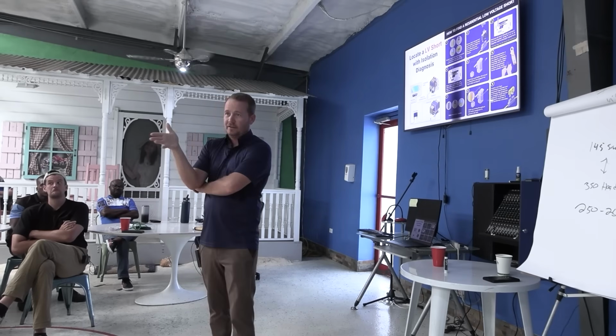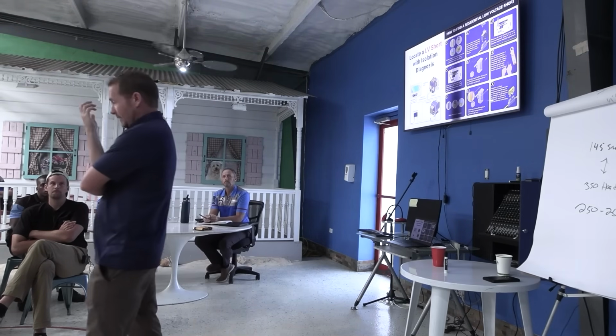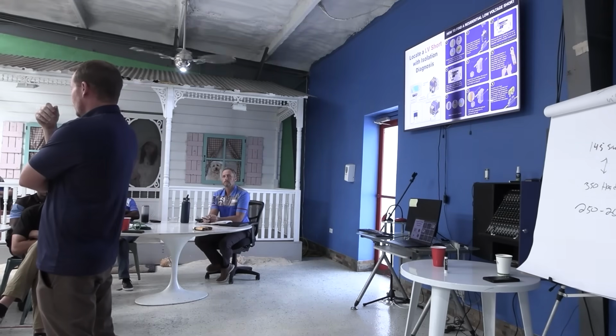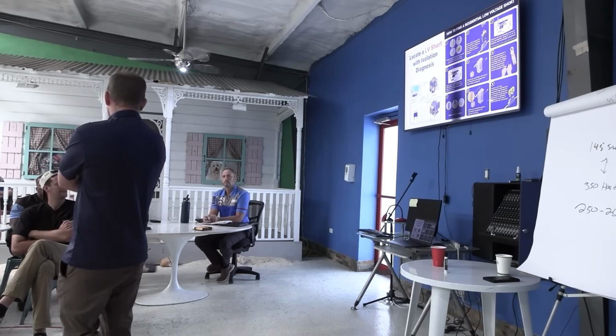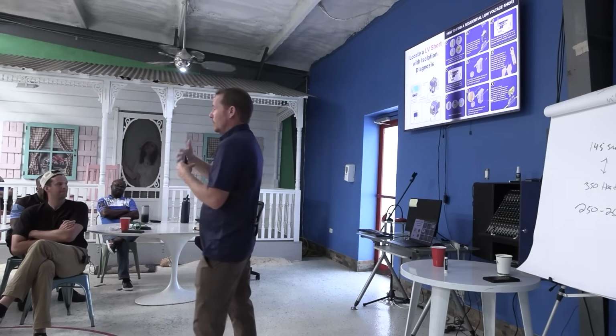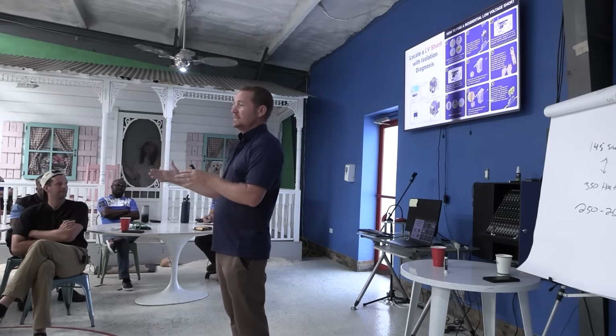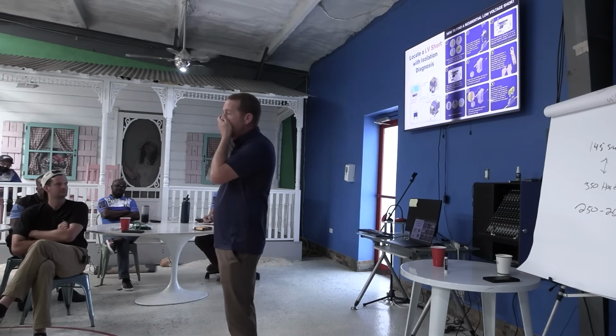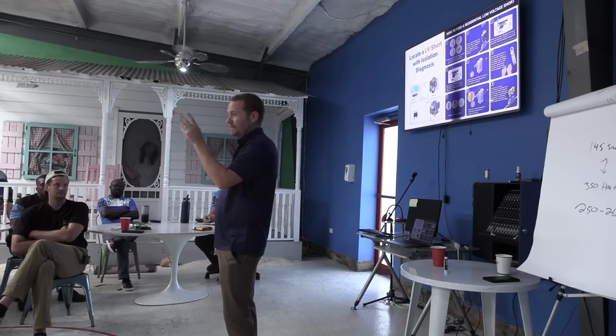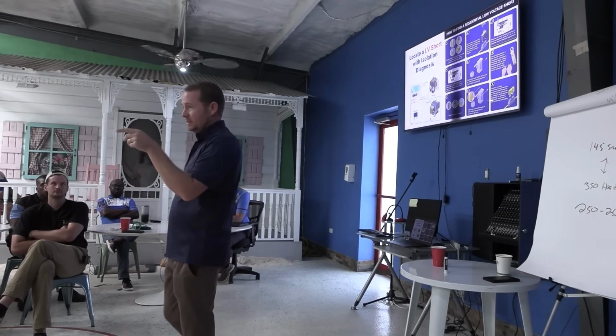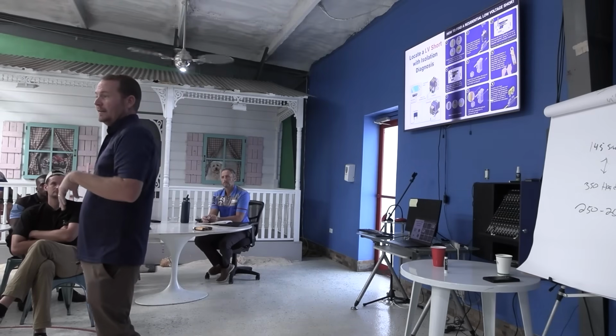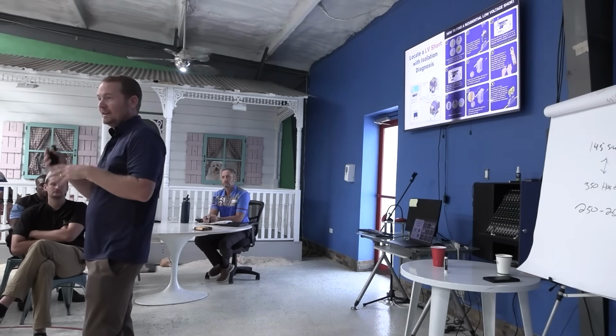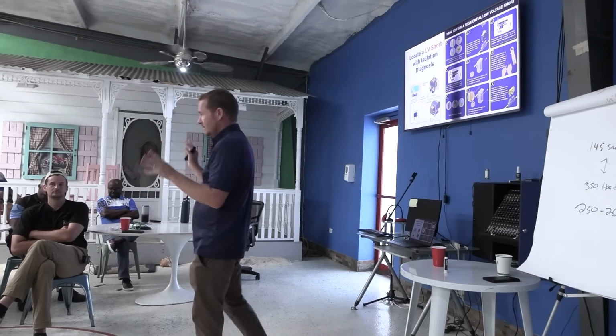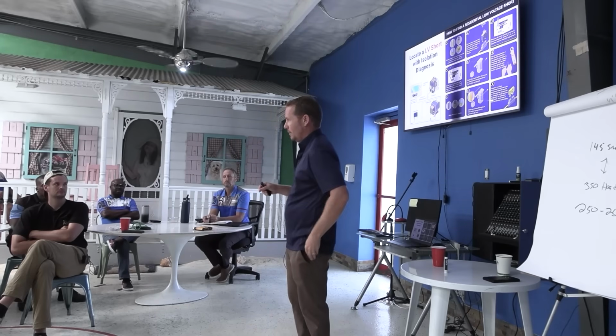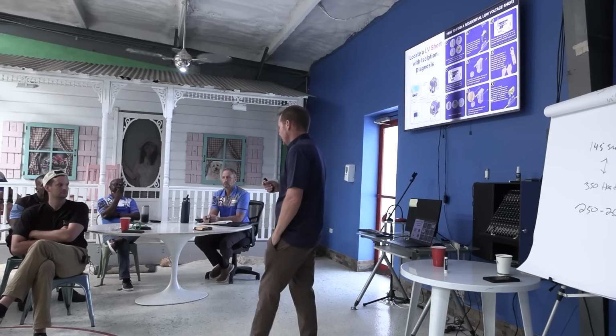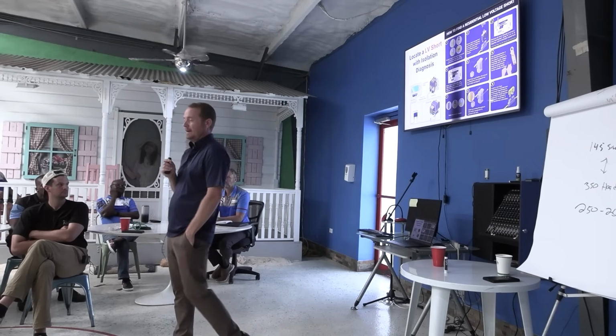That's kind of a neat thing, I like it. It comes up at times, and you run into some systems that draw high current, some multi-stage pieces of equipment that draw higher current. Those are often the same pieces of equipment that make fancy thermostats fail. So when Nest thermostats keep failing on you, it's because that Nest thermostat has an even smaller fuse in it, like a 1 amp fuse or something goofy like that. So when you draw a little higher current, they fail. When Nest first came out, this was a massive problem, we had them failing all the time because of that internal stupid fuse they had.